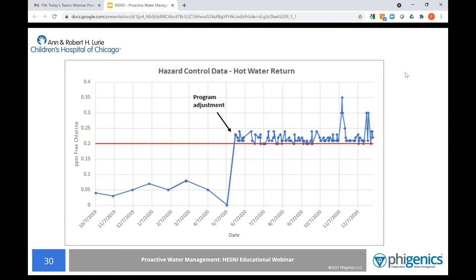What we ended up doing is, right around May 7th or probably early June, we started flushing the domestic hot water return. And you can see that in doing that, our free chlorine residual in the return water, and therefore the whole hot water system, increased to a level that was above 0.2. Our goal was to get above 0.2 because we know that 0.2 is generally a level that we've had success with, having that disinfection level and eradicating any type of bacteria or biologicals. So while a simple graph, this represents a significant accomplishment in our program. Next slide.